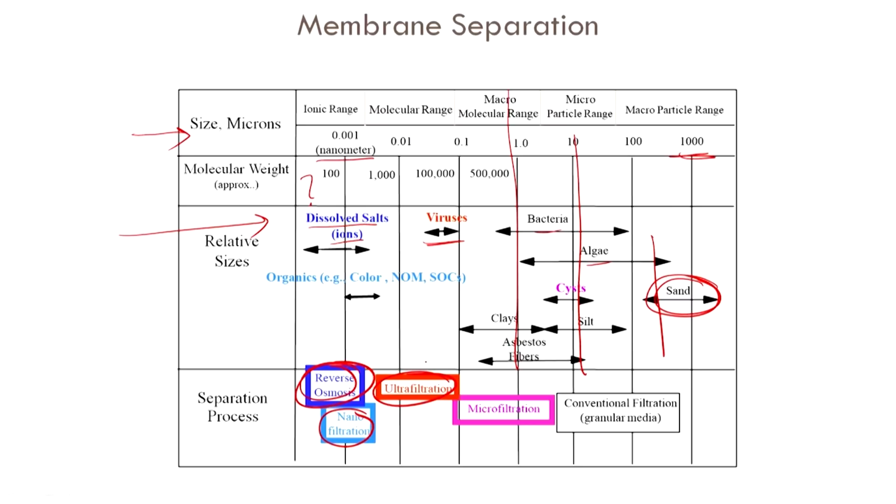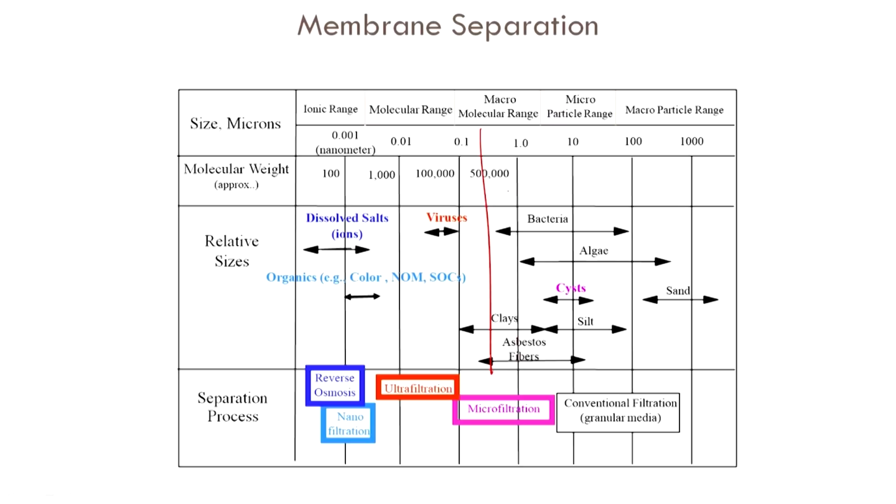But the gentleman there, obviously he was only showing a kind of sand filter, which will not help protect your RO membrane from choking up, because all this material that we have out here in this range will go and be deposited on your RO membrane and choke it up, right. So, if you are removing only the bigger particles, let us say till here, with your sand filtration, which is what the entrepreneur had out here.